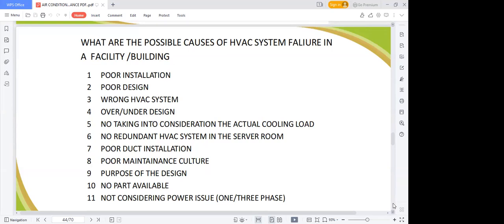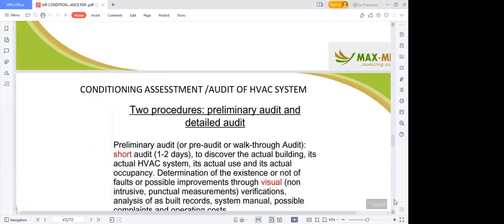Then if you want to buy, always consider if your design is within range. There's an option for one phase, there's an option for three phase. Please, I will advise you, if you have the option for the same capacity that you are choosing, go for one phase. One phase is always available in Nigeria. Three phase is never available, because if you use three phase, that means you have to run your generator to power your unit. Please, you need to consider all these factors I'm mentioning to you.